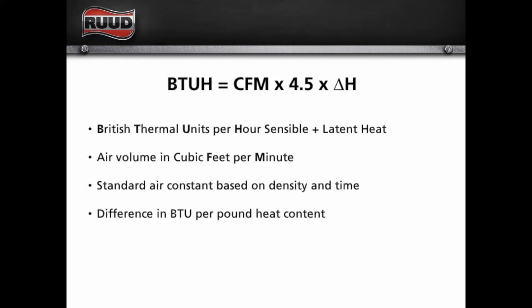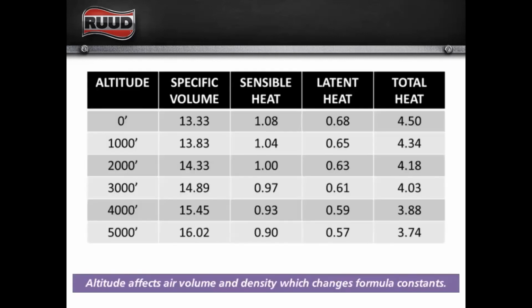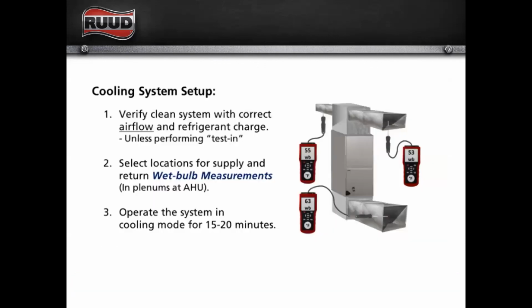We need to know exactly how many cubic feet we're moving so we can plug that number into the formula. We're always going to multiply by 4.5, and then we're going to multiply by the difference in enthalpy. And that 4.5 comes from this table, right? So if you're below 1,000 feet above sea level, right? So if you're higher than 1,000 feet, I don't know where in Florida you're measuring this, maybe on top of a big crane, I don't know, but this is where that 4.5 comes from. It's just a constant in this one. Am I wrong? Is there a place within the state that's 1,000 feet above sea level?